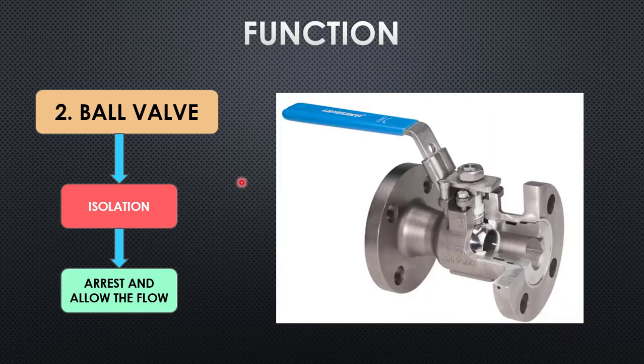The second valve is the ball valve, which is also used for isolation — the same purpose as the gate valve. A ball valve has a ball with a hole inside. When the lever is turned, the ball rotates so the hole is perpendicular to the flow, arresting it. Turning the lever again in the anticlockwise direction opens the flow.